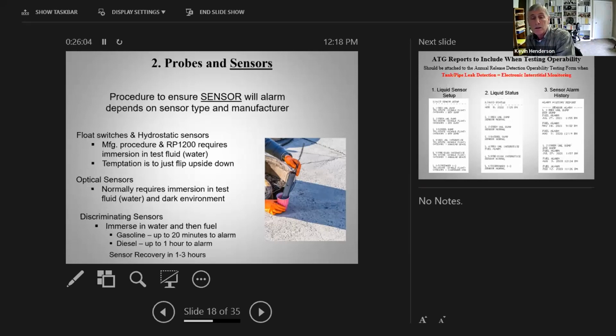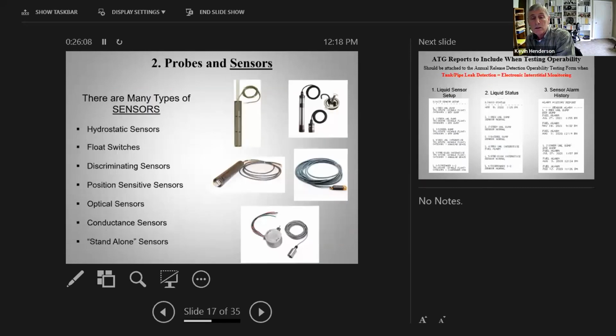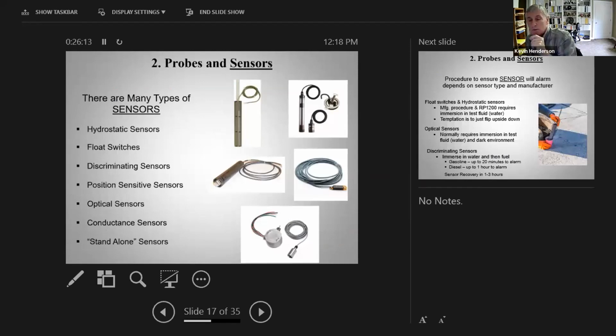The thing I wanted to mention about the middle far right picture, that's on a tank interstitial sensor, and this is for a fiberglass tank. If you're unlucky enough to have a double-walled fiberglass tank and you're doing interstitial monitoring on that double-walled fiberglass tank, then you know that pulling that sensor out of that interstitial of that tank and getting it back in can be real trouble. That is by far the biggest issue we have with doing sensor testing, these double-walled fiberglass tanks. I can't tell you how many times the little pull string has broken.